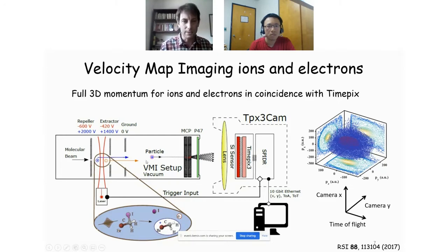But the basic idea is this: here's the velocity map imaging that I described earlier. Particles come and hit our detector here, which consists of a microchannel plate, which basically changes one electron or ion into something like 10 to the 6 electrons. Those 10 to the 6 electrons are then incident on a phosphor screen, which emits light. That light is imaged to the sensor of the TimePix camera. And the TimePix camera not only records the two-dimensional position of each electron or ion arrival, but it also records the time with a resolution of about a nanosecond.